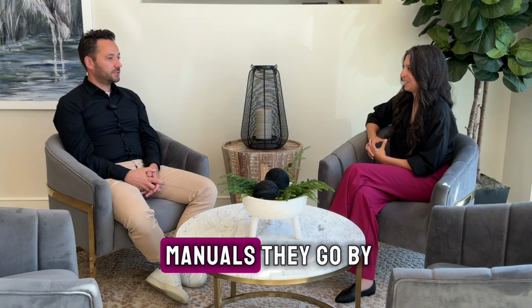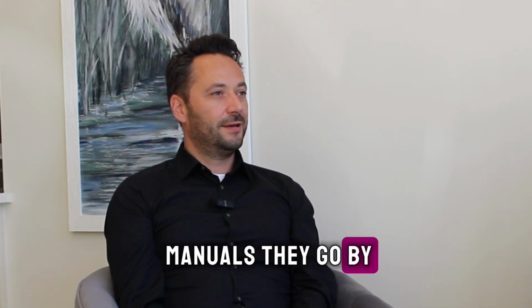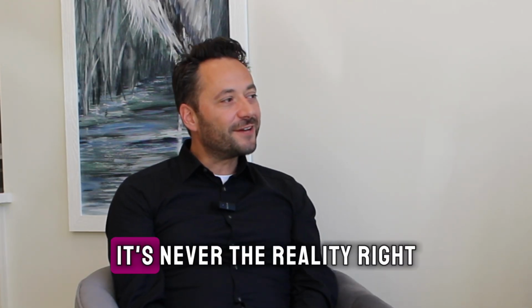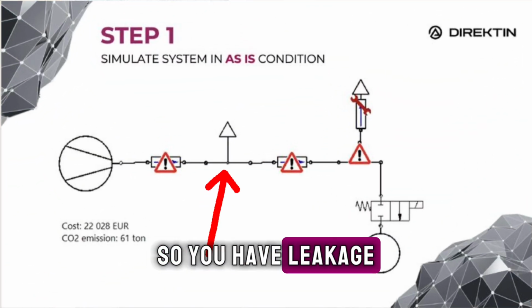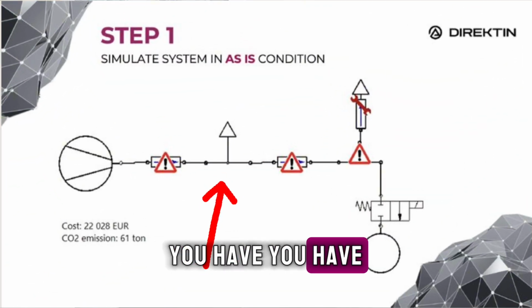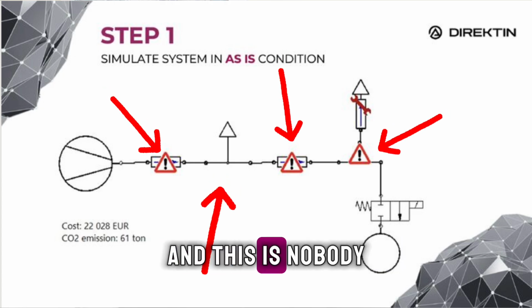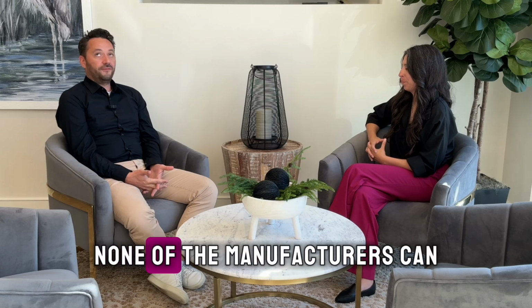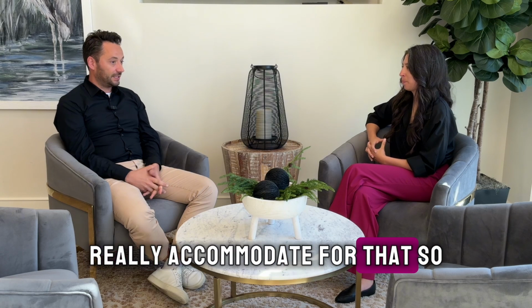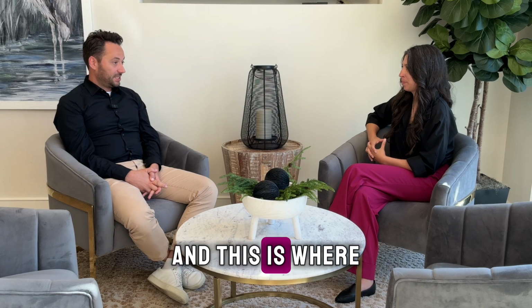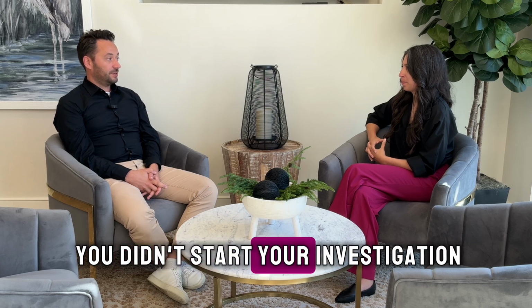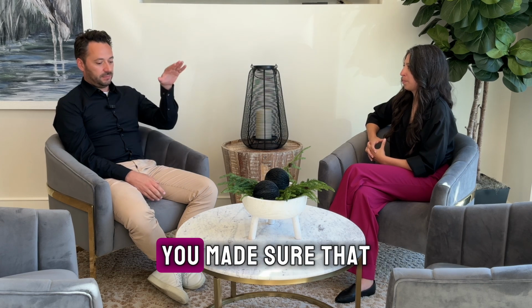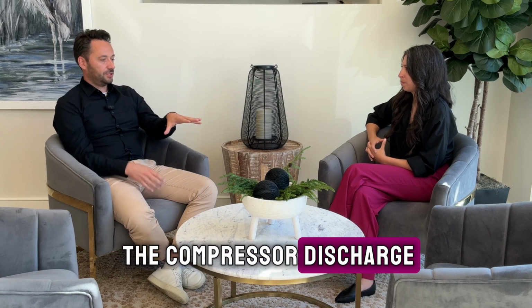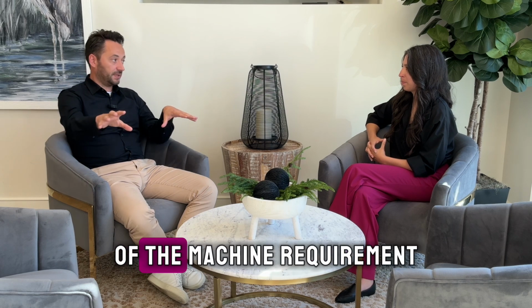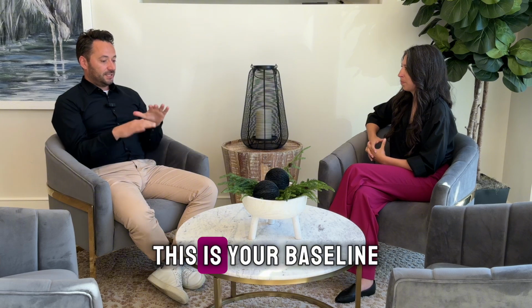or most of the manuals, go by lab conditions. It's never the reality, right? So you have leakage in the system, you have some pressure drops, and none of the manufacturers can really accommodate for that. And this is where you then start your investigation, right? If you made sure that the compressor discharge aligns with the machine requirement, this is your baseline. If this still doesn't match up, they need to look.